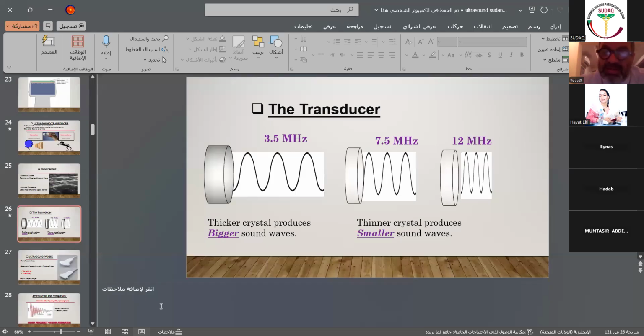So we know that there are many transducers. But for us, the most important transducer is the curved one, which has low frequency, usually from 3 to 5 megahertz. And we have a higher frequency one, which is the linear one, and usually it goes even to 25 megahertz now. And a few words about the transducer, about when I use this one and the other one. The curved one can go very deep, up to 35 centimeters. But at the same time, it doesn't give you a very good picture. It's called bad resolution.